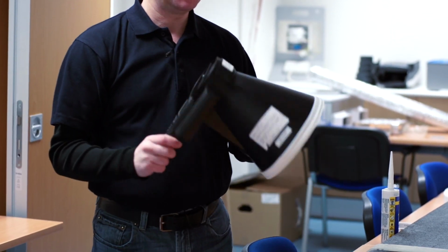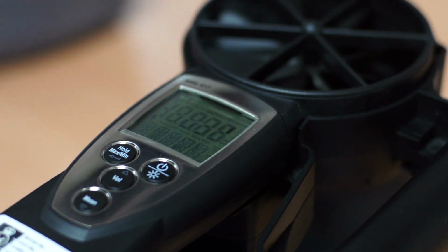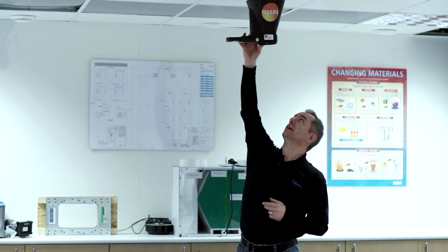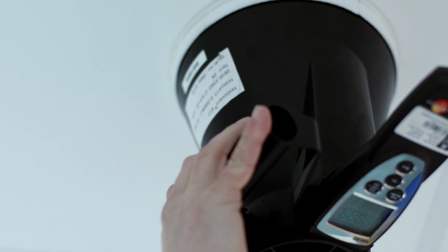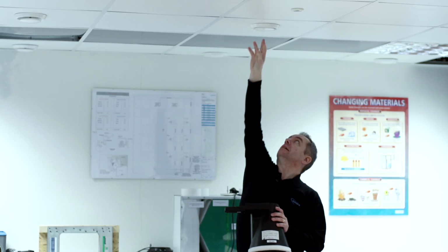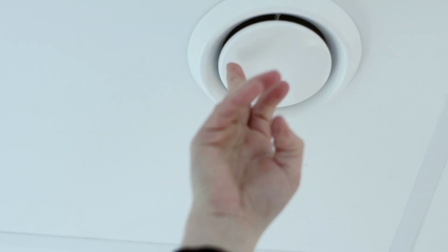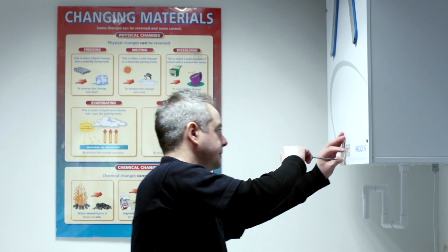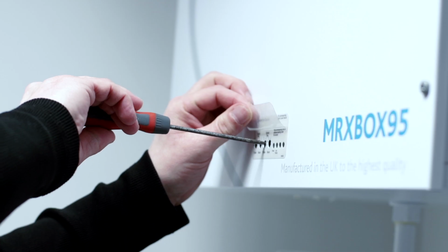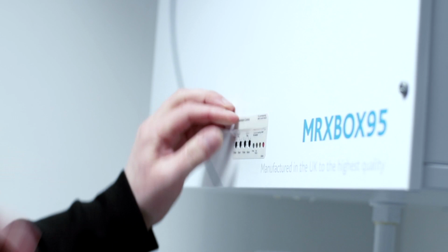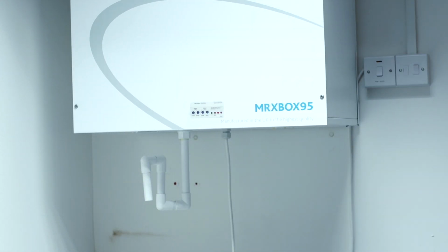This is achieved by using a hooded anemometer. Commissioning is a combination of adjusting the speed of the fan and adjusting the position of the air valves in the ceilings. The ideal scenario is to have the fan running as slow as possible to prevent noise breakout, but still achieving the design duty from each valve. Once the design airflow rates have been met, it's important that the air valves are locked off in their commissioned state. All airflow readings should then be recorded in the commissioning certificate found at the back of the Domestic Ventilation Compliance Guide.